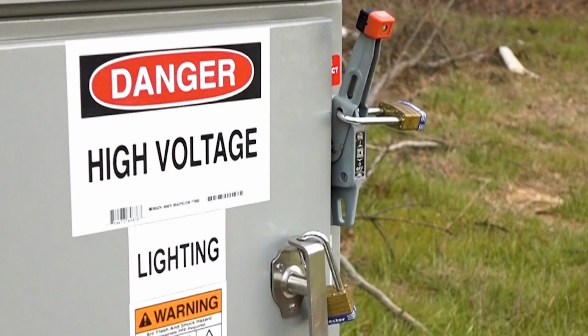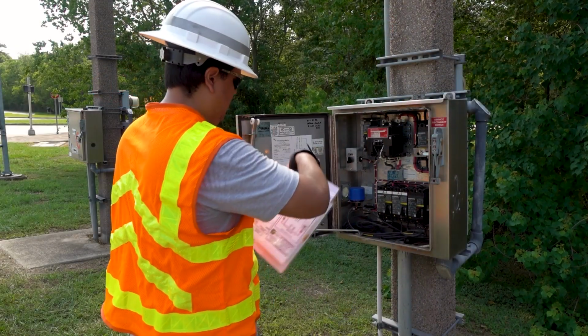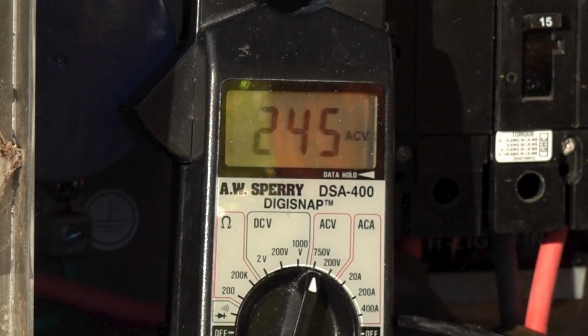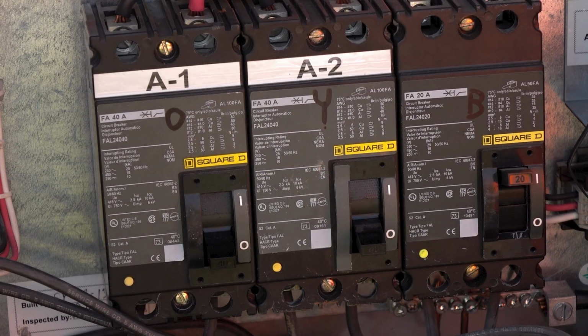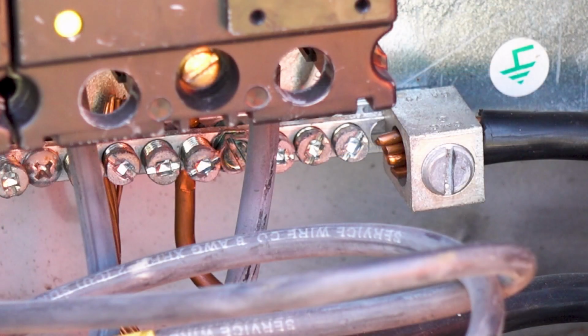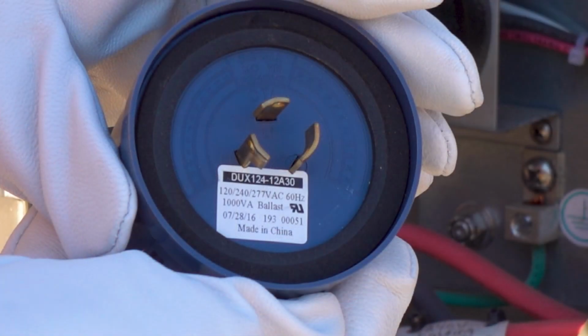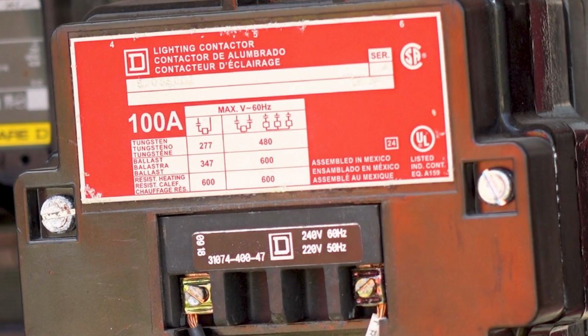The main disconnect is drilled and a lock is installed. Laminated as-built plan sheets are included. Voltage readings are within specifications. Main and branch breaker sizes are as specified on the electrical service data chart. Conductors are properly terminated. Photocell brand and model are as specified by the MPL. Lighting contactor brand and ampere rating are as shown on the line drawing.